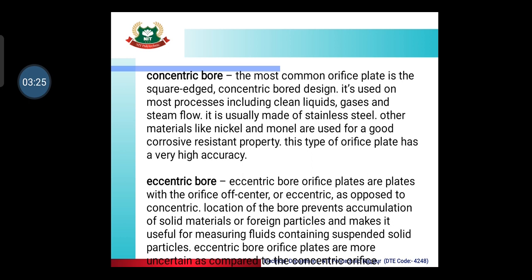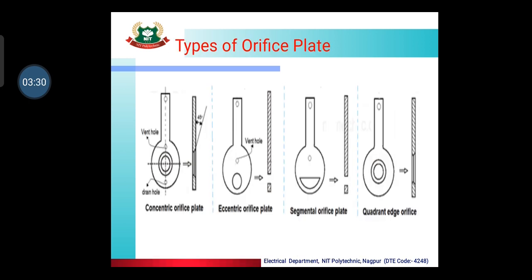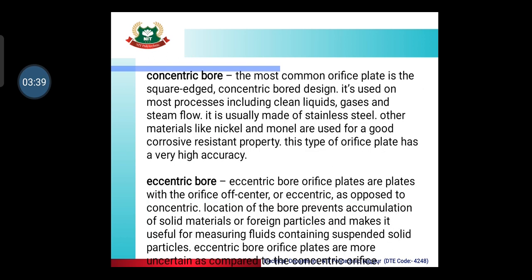The most common orifice plate is the square concentric bore design — you can see the concentric bore design, which means the hole is at the center. The second type is the eccentric bore orifice plate. Eccentric bore orifice plates have the orifice off-center or eccentric, as opposed to the concentric location. This offset location of the bore prevents accumulation of solid material or foreign material particles, making it useful for measuring fluid containing suspended solid particles. Eccentric bore orifice plates are more uncertain compared to concentric orifice plates.